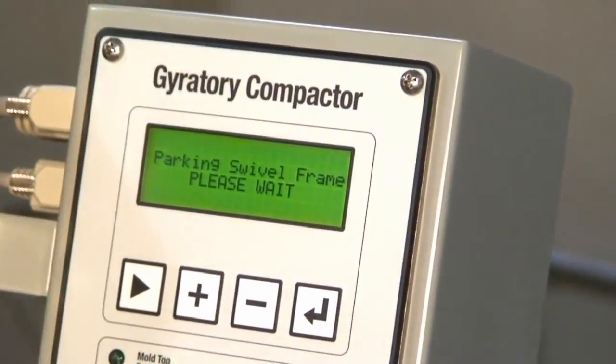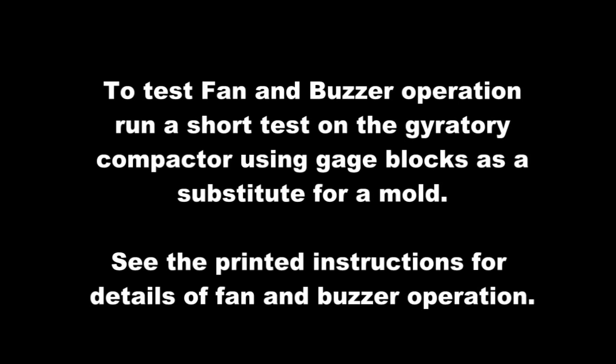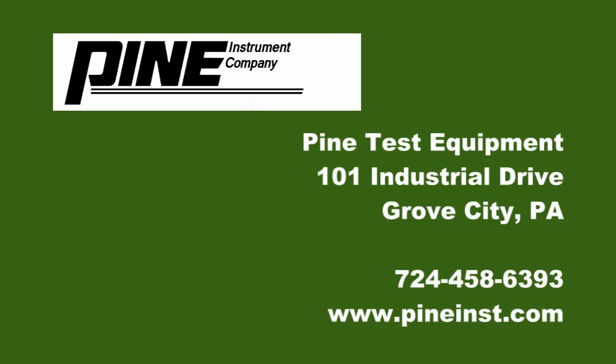If you want to test the fan and buzzer operation, just run a short test on the gyratory compactor, but use gauge blocks instead of a mold. See the printed instructions and you'll see details of how the fan and buzzer are supposed to operate. Thanks again. If you have any questions, please give us a call.